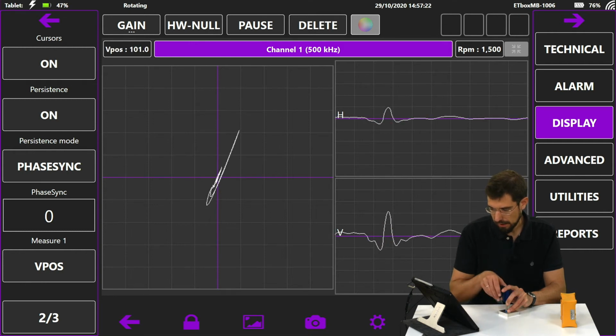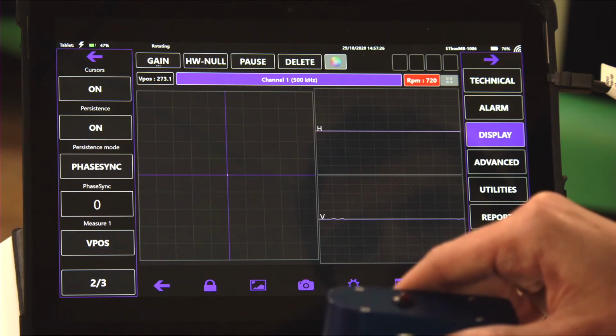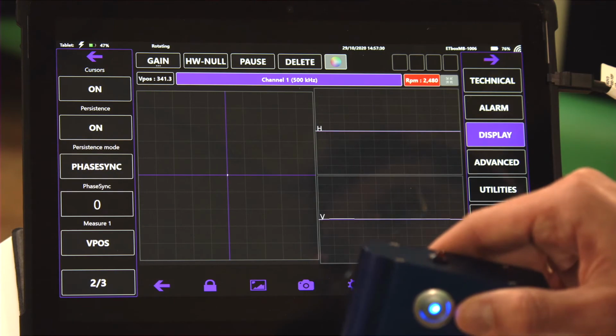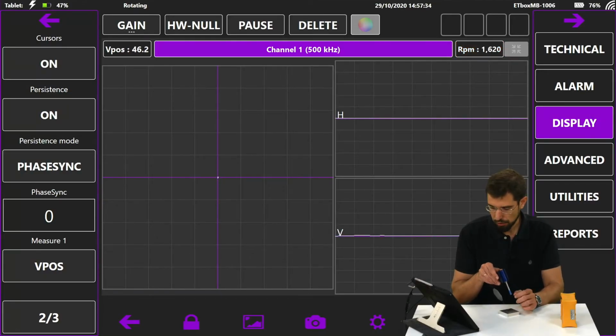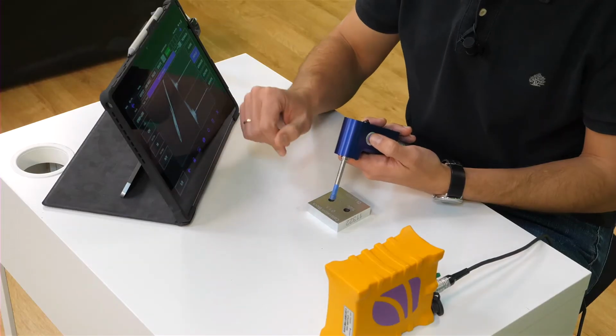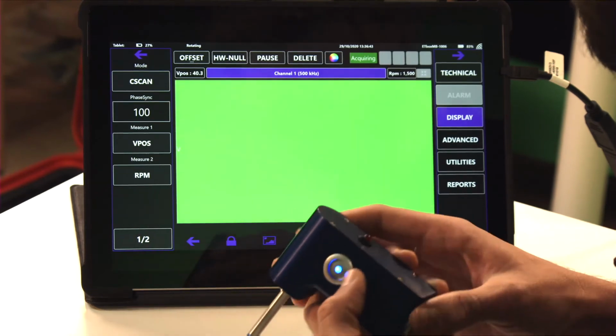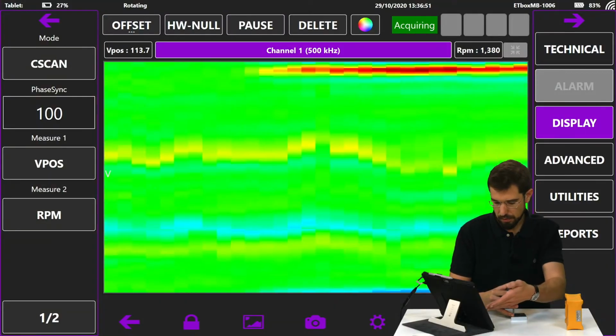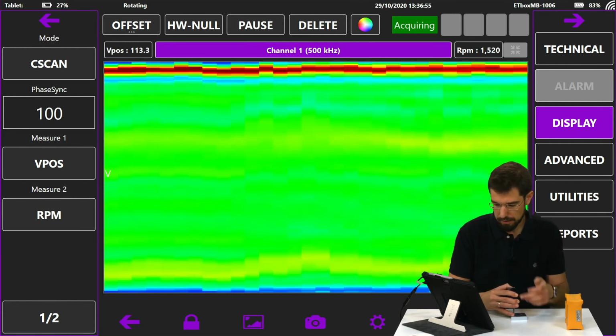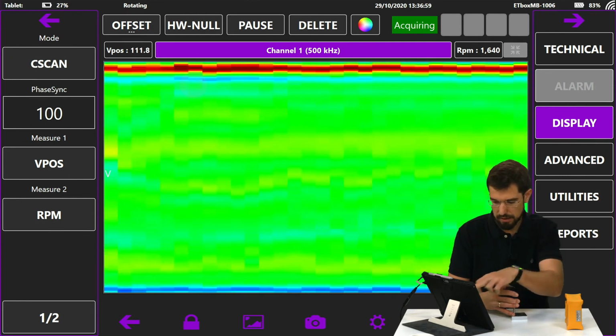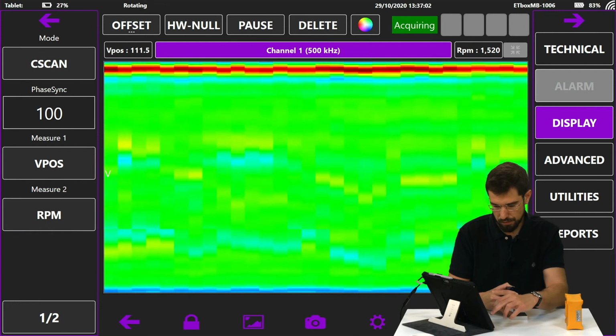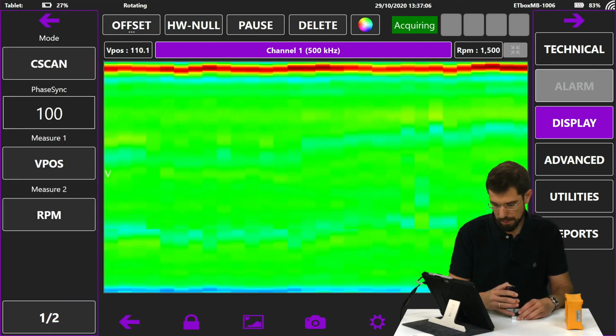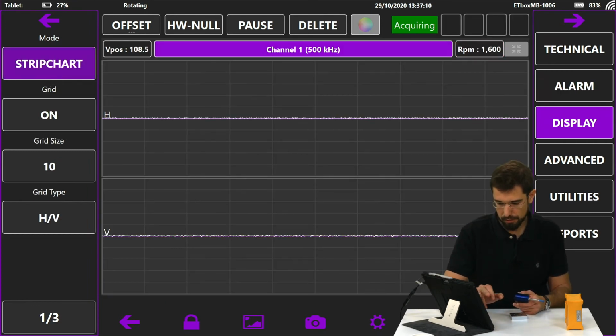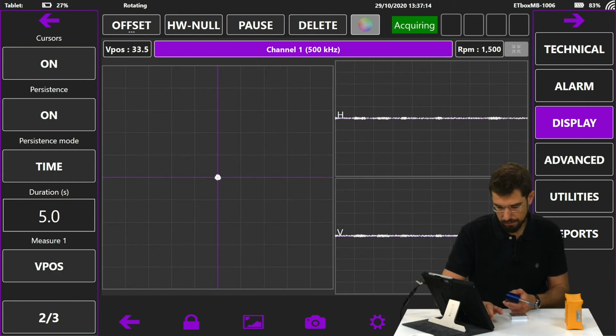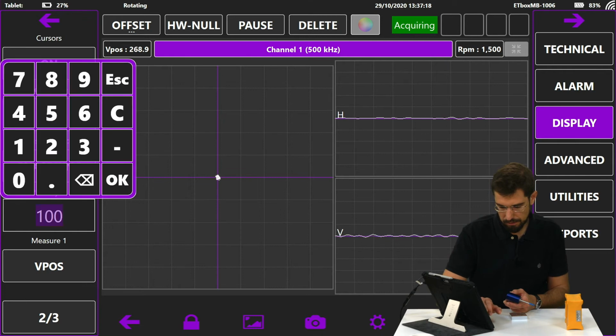On the other hand, in RPM, if we check the revolutions that are configured when the probe stops rotating, it turns red and an alarm goes off saying, "Be careful, we are having a problem in the rotation. The control term is not being met." Another difference that we find is that right now it would be activated. We have a C-scan view available. With this C-scan view, we can look at the timeline and the 0 to 360 degree line. There we would be looking at the notch. If we change, okay, well, we go back to our normal view with phase sync and 0.